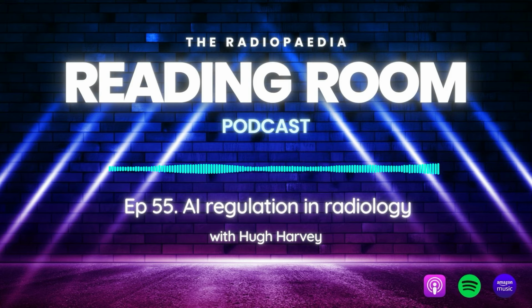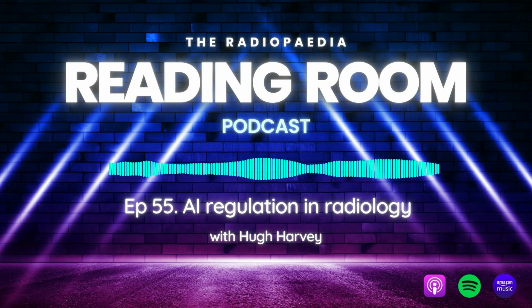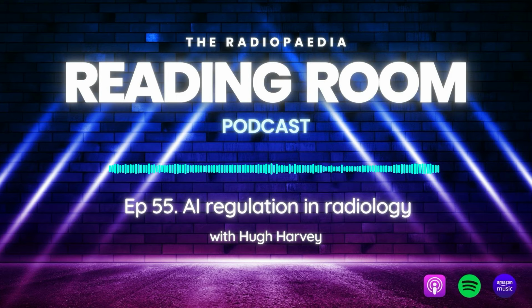One of the things about regulation currently is that only fixed algorithms are allowed on market, but obviously AI can perform best when it is iterated upon and updated. So there needs to be a formal plan for implementing changes based on your post-market surveillance. But also there's a new regulatory paradigm, not yet in force, called predetermined change control plans, whereby data aggregated across sites, performance data, can be used to retrain or tweak algorithm performance thresholds and then update. So do have a think about how you would like to develop a process and a quality assurance process to iterate on your algorithm and improve the performance over time.